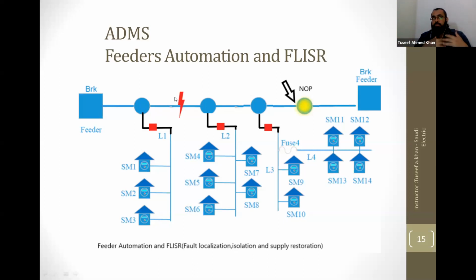In our case, we are using ADMS in Riyadh City. We can decide where our fault is in 2 or 3 minutes. After that fault localization, immediately these two RMUs will be switched off remotely and automatically if you have set it to auto. This means your fault is isolated.